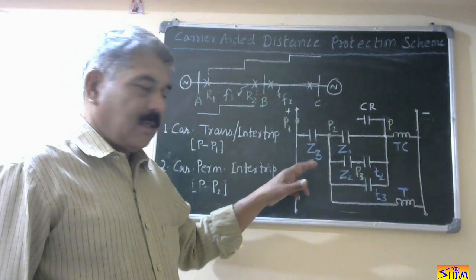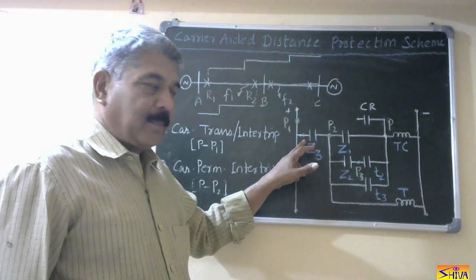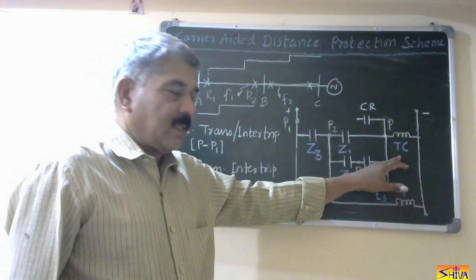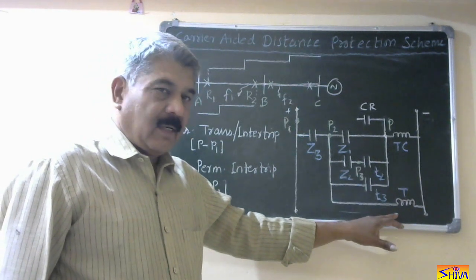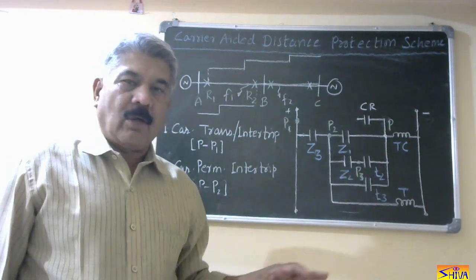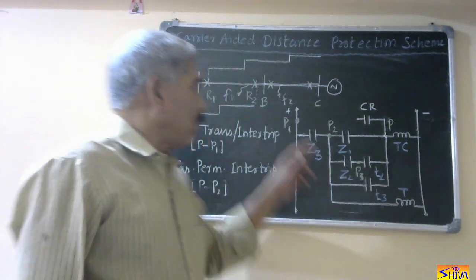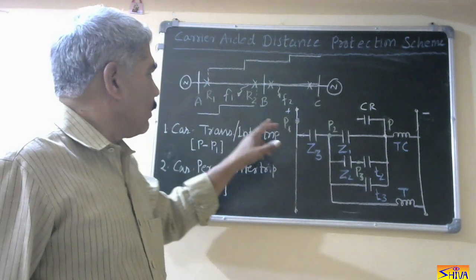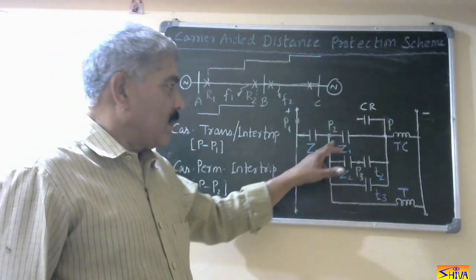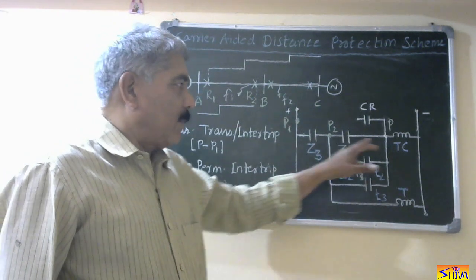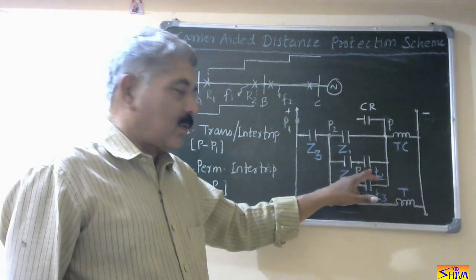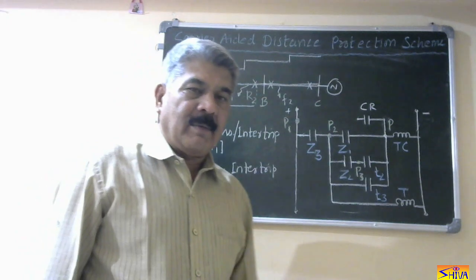I have already explained it, but let me revise. This is the contact of the third element Z3, first element Z1, and second element Z2. This is the trip coil of the circuit breaker. This is the timer coil — T2 and T3 — which are normally open contacts of the timer element. So for fault F1, which is in the second step, Z3 and Z2 will close while Z1 is open. So the trip coil will not be energized instantaneously; the timer circuit will be energized and after time T2, this contact will close and the trip coil of the circuit breaker will be energized.